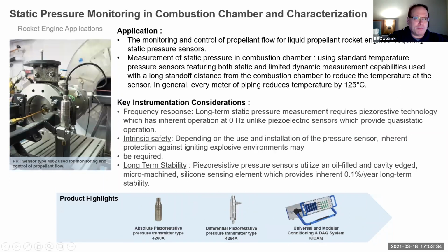There's also measuring static pressure for long periods of time, and piezoelectric might not be optimum for that. In some cases, piezo-resistive technology is used on a standoff to reduce the temperature of the measurement. So in some cases you need more than just a piezoelectric solution—a piezo-resistive solution to measure static pressure in the combustion chamber.